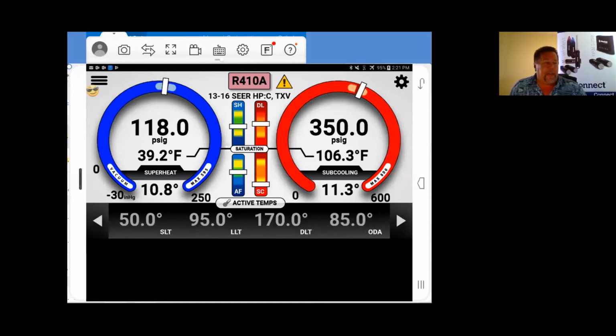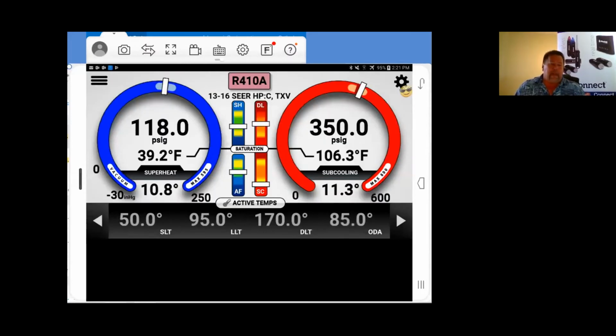Now, if you keep getting that, but everything seems to be running well, you've got a good split, temperature's cold coming out of the vents, if you got 55-degree supply air, 75-degree return air, and everything seems to be going well, but it keeps telling you that, you probably have a bad probe placement. And right up here is that troubleshooting, and a lot of people like to see it, some people don't. So you can always turn that off simply by going into your gear side menu, open up tools, and turn troubleshooting off, and you won't see that. A lot of guys like it, a lot of guys don't.